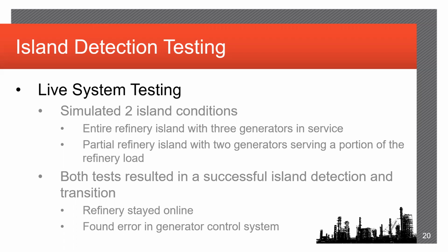Once the refinery came back online, and before they actually really started to bring up all of their refining processes, that's when we were able to do 2 actual islanding events. And it's possibly a bad choice of words on my part, because I say simulated 2 islanding conditions. Well, what actually happened is the system was online, and we manually tripped the circuit breaker that would island the entire refinery. And that's how the test came about on the live system. And then later on, as I say here, we did a partial refinery island with 2 generators in service.